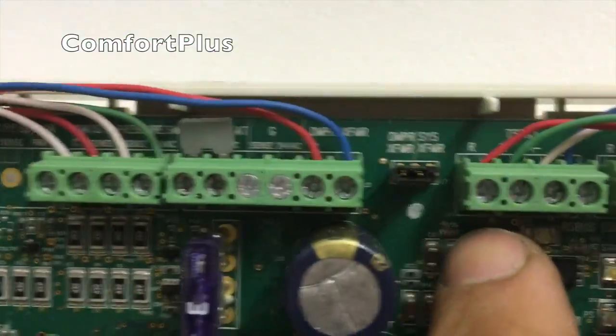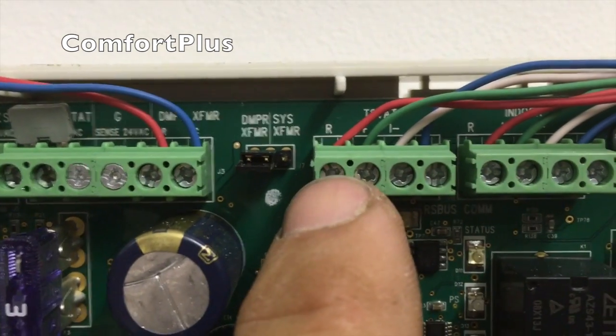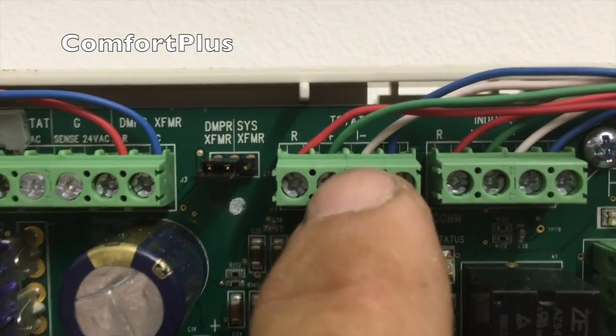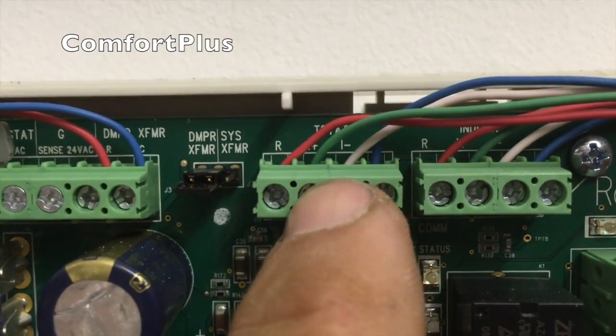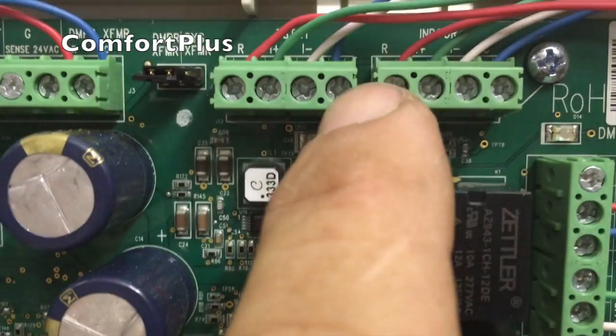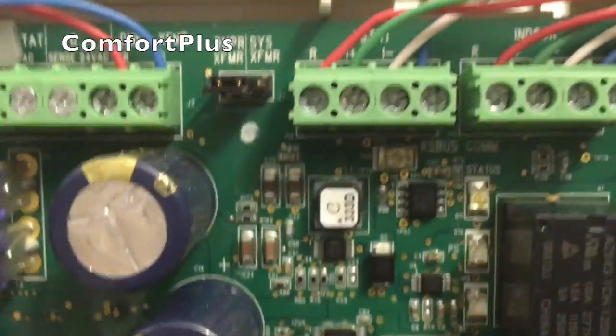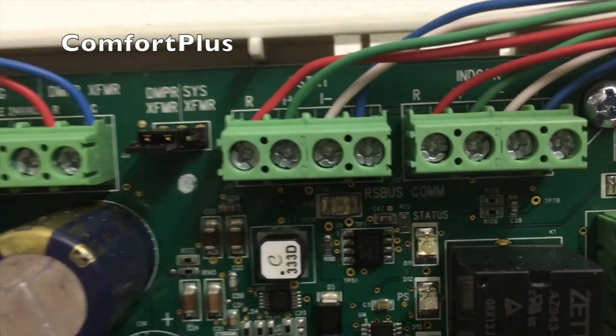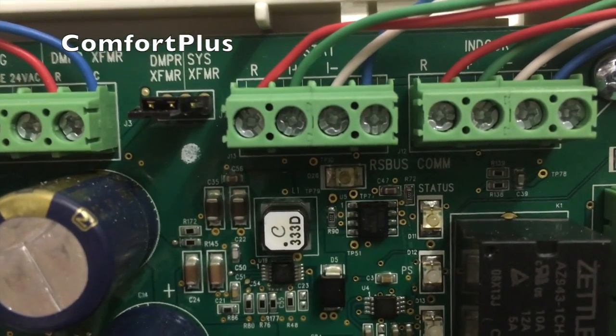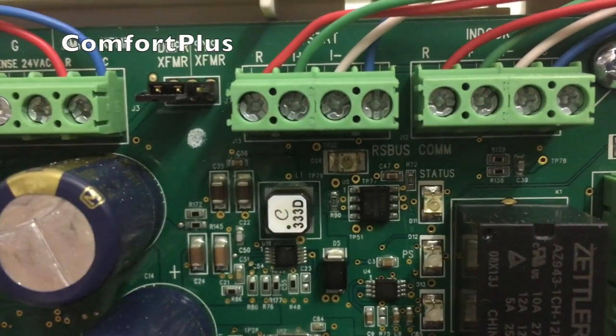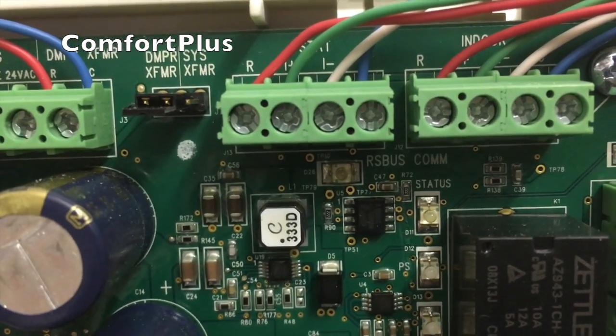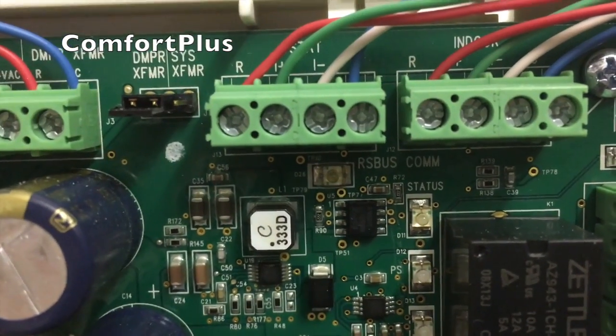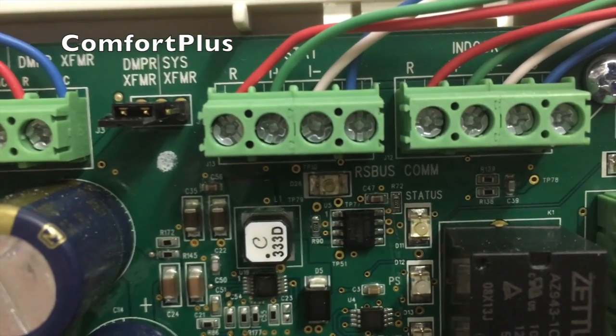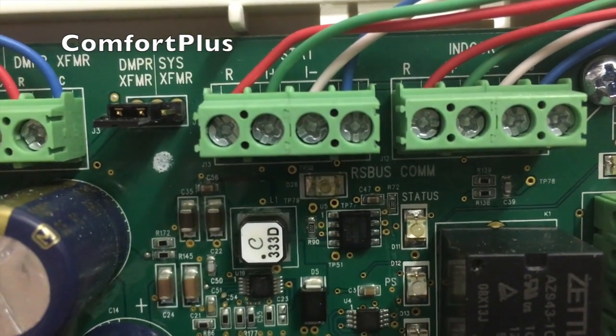Up here at the top, this connector is called thermostat, which is going to the actual ComfortLink thermostat. You have your R, they call it a data plus and a data minus, and then a common. And then beside of it here it says indoor unit. So it's just a 4-conductor cable that runs between this panel and the actual board in the air handler. And then the outdoor unit connects to the panel in the circuit board that's actually in the indoor unit, and I just have to run a 4-conductor cable between the indoor and the outdoor.